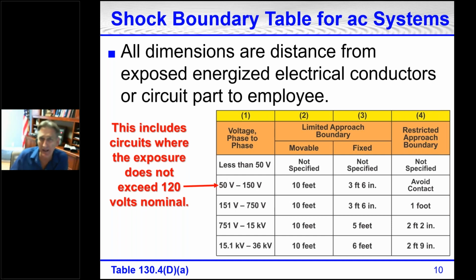Most of the time, unless what you're doing is utility type work, overhead lines, most of the time in industrial plants, your equipment is going to be fixed. So the limited approach boundary for both 120 volts all the way up to 750 volts is 3.5 feet. Then for 151 to 750, the restricted approach boundary is 1 foot.